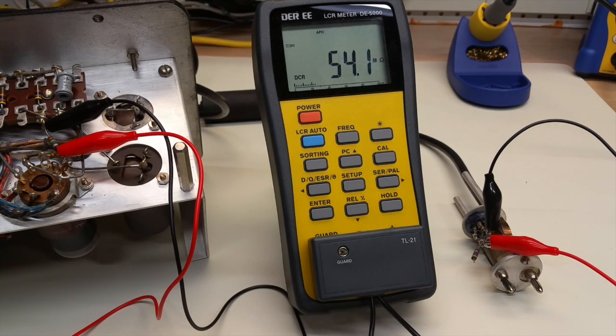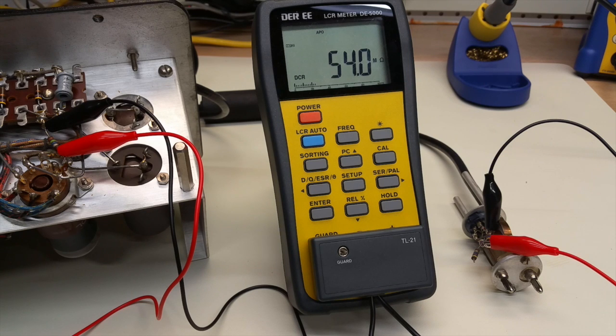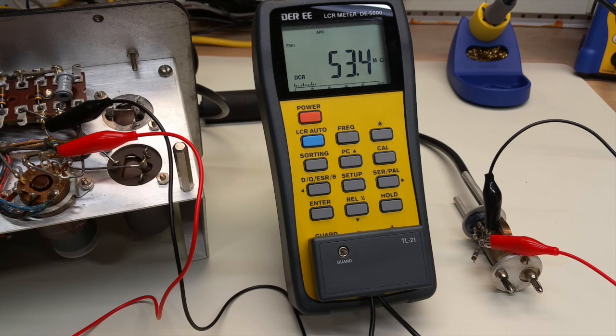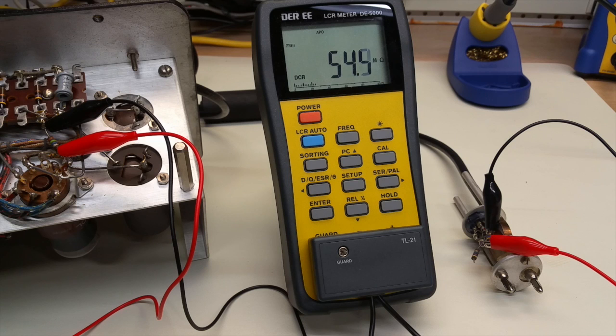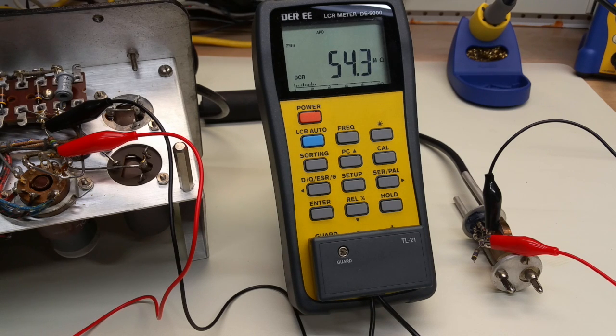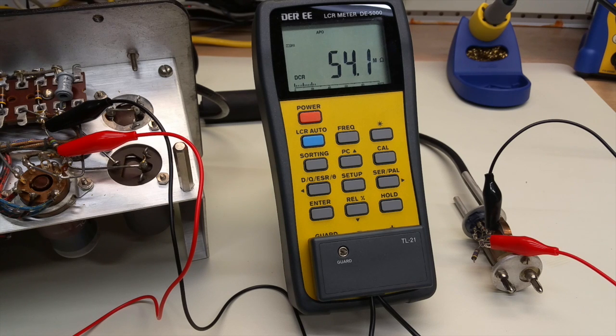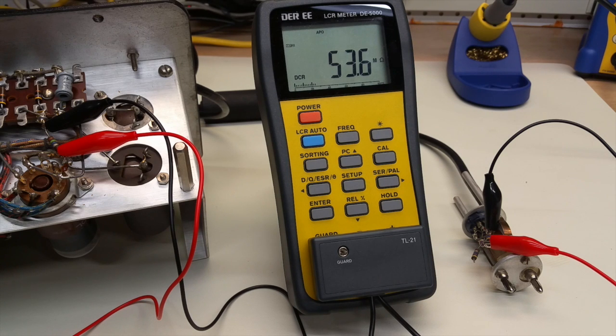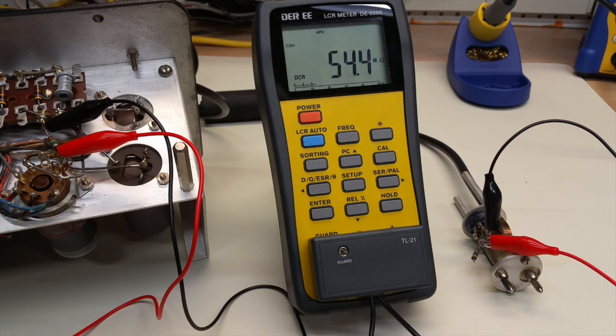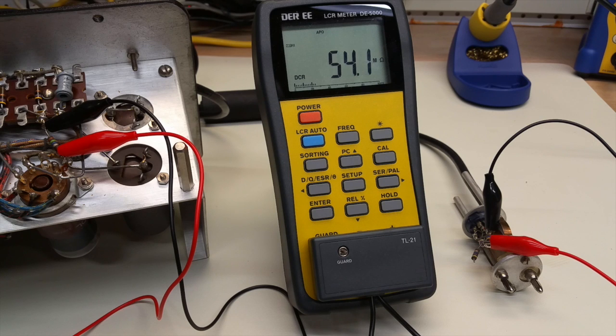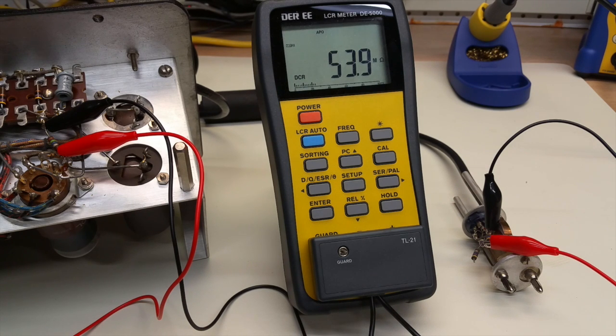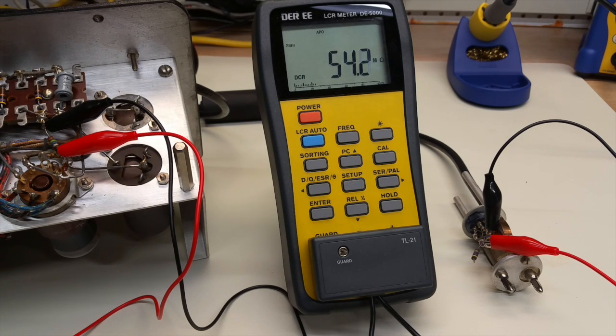This is the measurement of one of two like value carbon composition resistors in the active probe. The color code on those resistors translates to 47 megaohms each, with again a 10% tolerance. 10% tolerance for these resistors works out to be 51.7 megaohms. You can see that this resistor is measuring closer to 54 megaohms, so this resistor is out of tolerance and needs to be replaced. The second resistor is similarly out of tolerance, in fact more so, so those will be replaced as well. And what I'm going to do is actually replace all of the carbon composition resistors in this instrument, because there aren't that many of them, and I can get the values from online vendors.